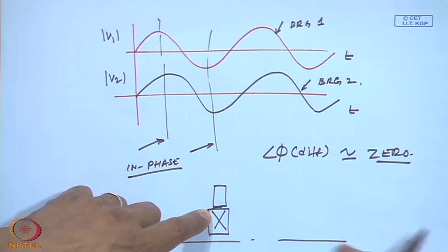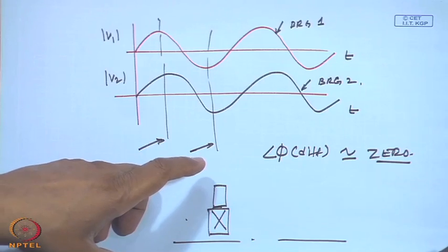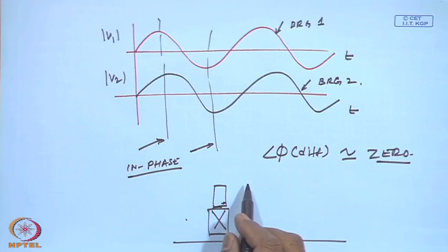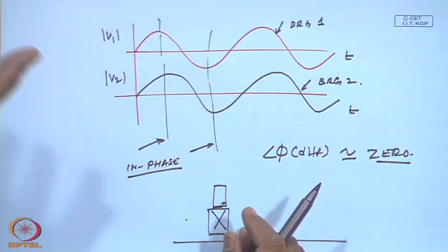Suppose the shaft had some other problem, like things were loose, the shaft had a crack, or shafts were misaligned. All these vibration signals are going to come into this accelerometer here. So, these are the diagnostic techniques or routines which we have to follow to ensure that it is unbalance and not looseness or misalignment or a cracked shaft.